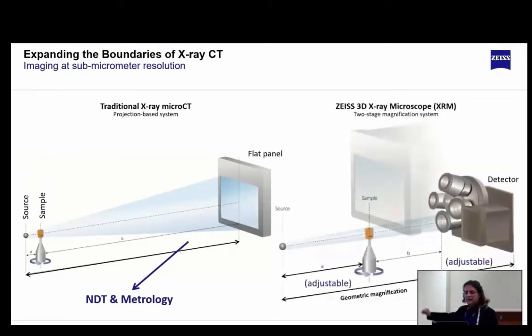And if you remember, the main difference of the so-called X-ray microscopes as compared to the traditional projection-based CT systems is that they include a set of lenses. And those lenses are going to give you the extra magnification capabilities, that by changing the optical magnification, it's going to give you extra room for that resolution. The geometrical magnification is still there, but the advantage of the optical magnification is that it allows you to still scan larger samples without destroying them to try to get the best resolution that you could, which would be the case of a traditional X-ray system.